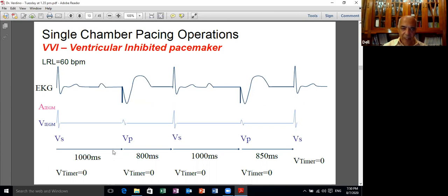So here this complex is a junctional complex or a ventricular event sensed by the pacemaker. There is a timer in the pacemaker which brings the timer to 0 when it senses anything, and then it starts to count 1000 milliseconds. Where did we get the 1000 milliseconds? 60,000, which is the number of milliseconds in one single minute, divided by the lower rate limit, which is 60, is 1000. If 1000 milliseconds elapse and nothing is felt during this period, then the pacemaker throws a spike and paces the ventricle. Now here there is an atrial event. Obviously, the pacemaker will not feel this atrial event because there is no atrial lead. And after this spike, the pacemaker timer will come down to 0 and start to count 1000 milliseconds.